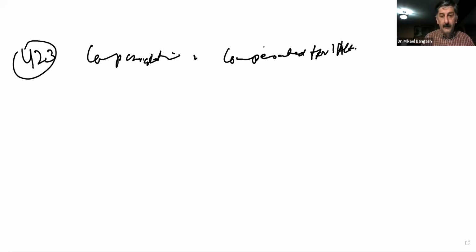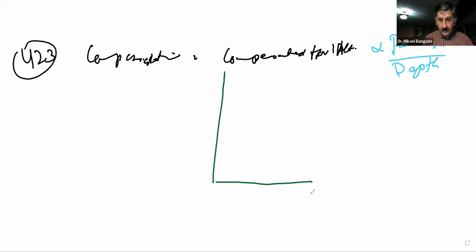Where we mainly can say it's directly related to the path length, or in this case, called depth. Which mainly means that as the sound reflects from greater and greater depths, you're going to have more and more compensation, and that's why we have a curve that may look something like this to compensate.